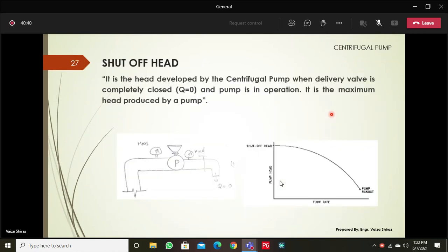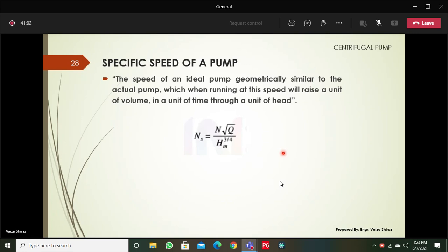The shut-off head is the head developed by the centrifugal pump when the delivery valve is completely closed and the pump is still in operation. Closing the delivery valve and measuring the head on both suction and delivery sides gives the maximum head produced by the pump. Next is the specific speed of a pump, given by the equation N√Q / H^(3/4), which gives the specific speed and is used in pump design.